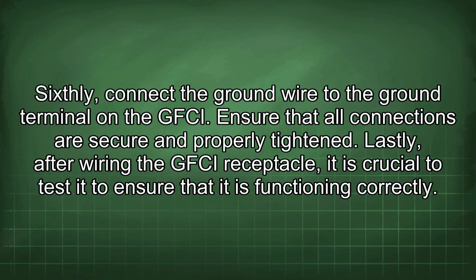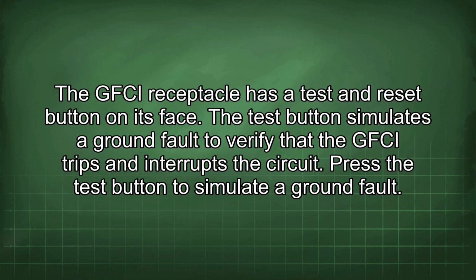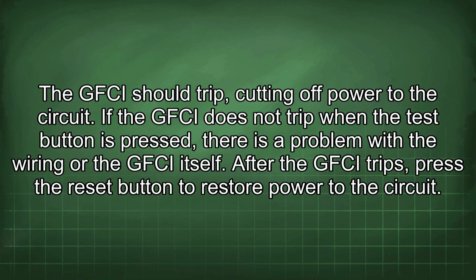Lastly, after wiring the GFCI receptacle, it is crucial to test it to ensure that it is functioning correctly. The GFCI receptacle has a test and reset button on its face. The test button simulates a ground fault to verify that the GFCI trips and interrupts the circuit. Press the test button to simulate a ground fault. The GFCI should trip, cutting off power to the circuit.